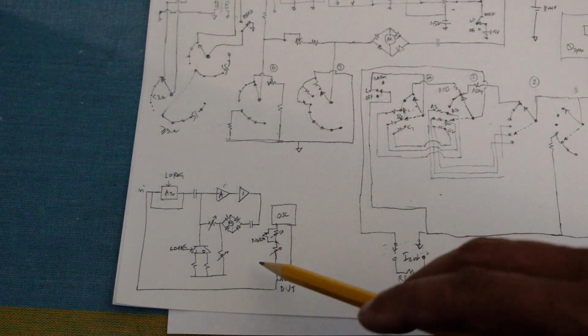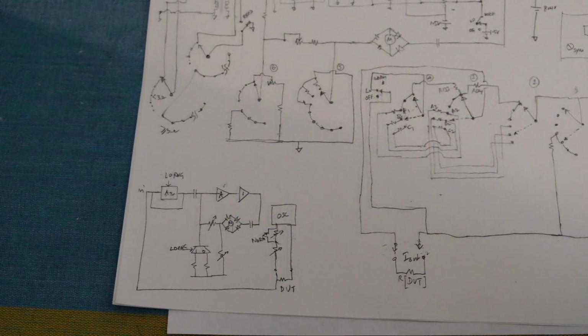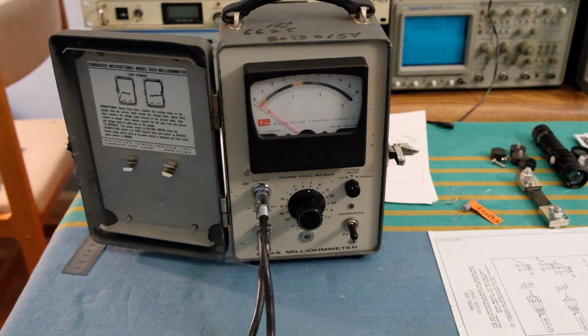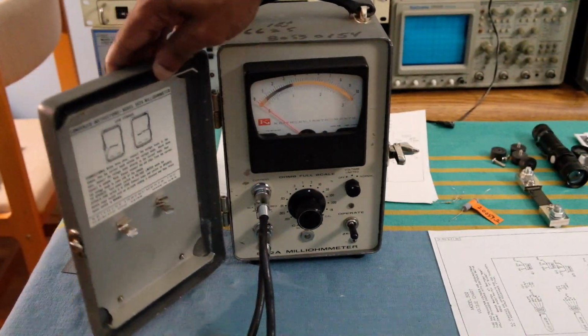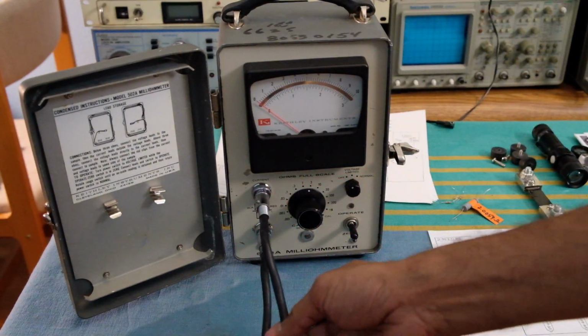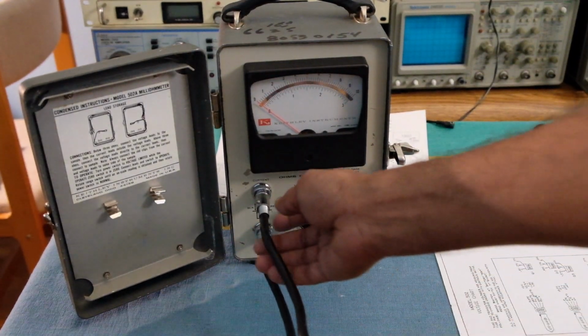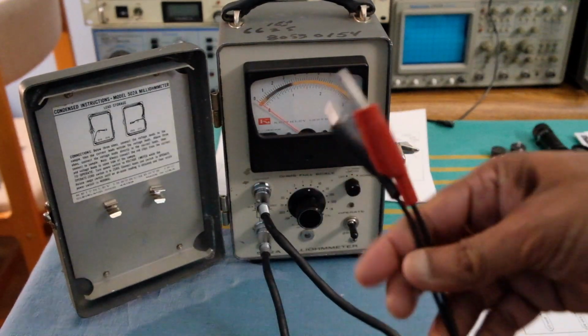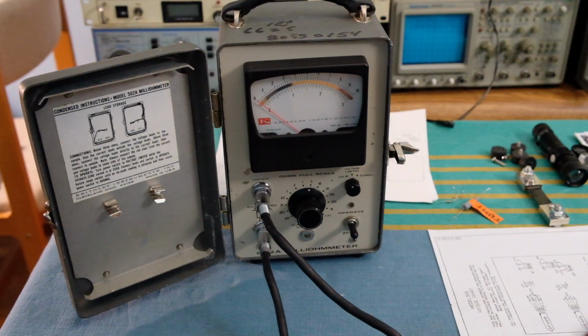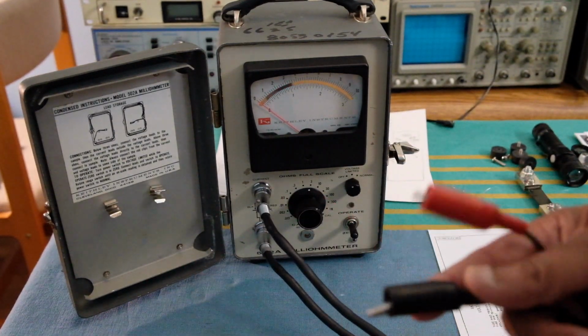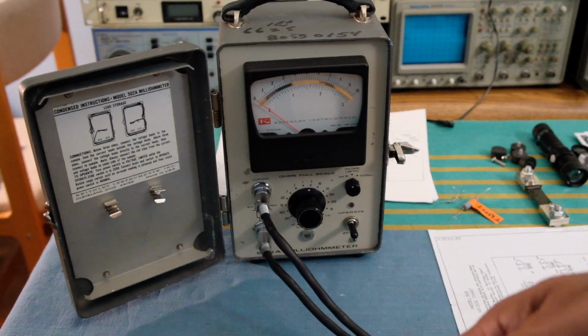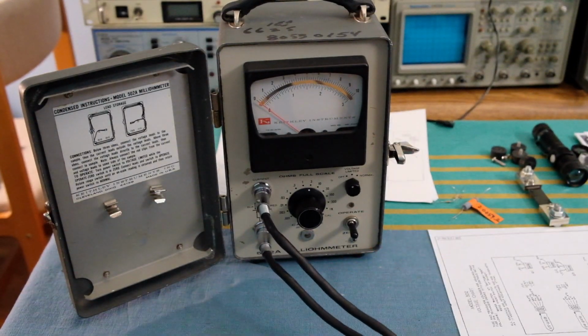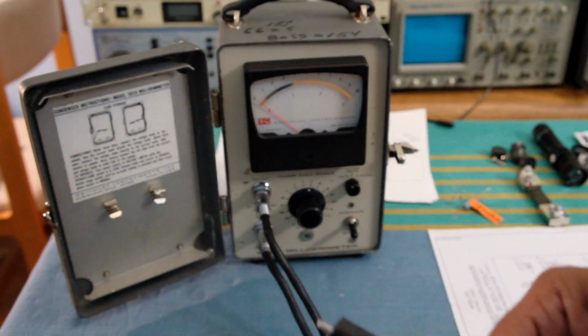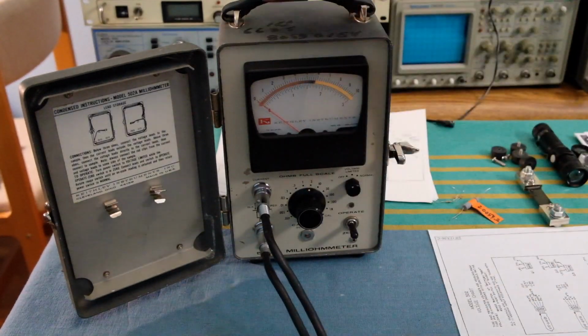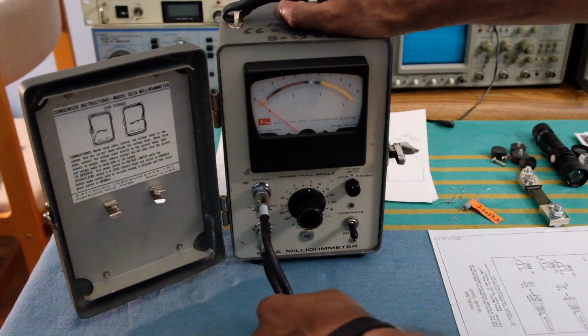Here is the same thing I showed on the board, which is a simplified version of this guy. Instrument over here, it's got a nice case and it can be closed, and the leads over here, which are the measurement leads. This is the current output, and there are two, as you can see, there are two plugs here, jacks, and then similarly for the voltage. Unlike the other Kelvin clips where these are joined together, this is more independent. I like this feature because you can put the current input wherever you want, and then the voltage wherever you want, close to where the measurement should be taking place. That's some advantage here, and it's really solid, good terminals here.